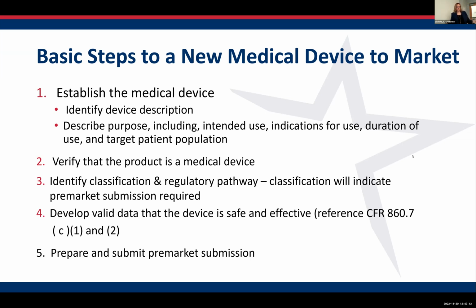Okay. So just to go through this, first you have your idea. The first thing you need to do is go back to the description of what a medical device is and make sure that what you have is truly a medical device, with all the characteristics of a medical device. So you're verifying that that is true. Then the next step is to identify the classification and the regulatory pathway. There's lots of different ways you can go, so you have to figure out what that is. The classification, whether it's class 1, class 2, or class 3, will indicate whether you need the 510K or the PMA, or whether you don't need that. You need to develop and make sure you have really good data that supports the fact that it is safe and effective. It does what you say it does.